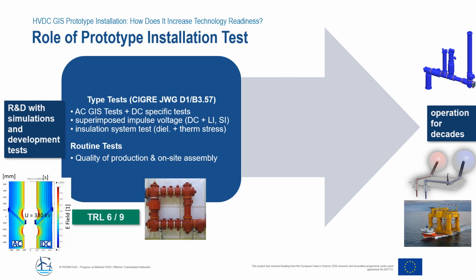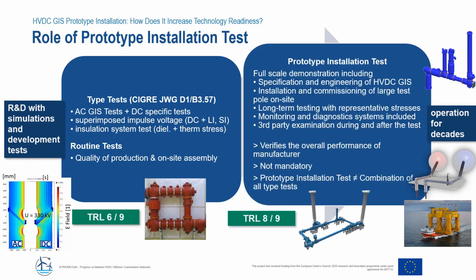And to bridge this gap to the real in-service operation of the HVDC GIS, the prototype installation test is proposed. It is a full-scale demonstration, including specification and engineering of an HVDC GIS installation, the installation and commissioning of a quite large test pole, on-site long-term testing for more than a year with representative stresses, dielectric, thermal, mechanical. We have monitoring and diagnostic systems included in the test pole and third-party examination of all the steps.